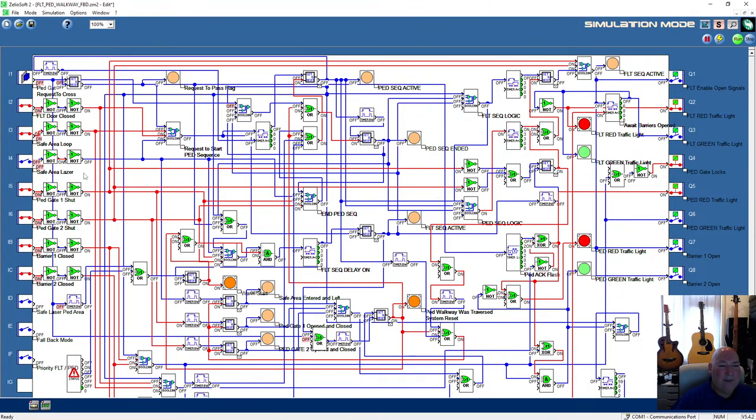So what we need to happen is if it times out, I've got to be so careful, because that's why we need a separate loop. At the minute, this loop does the pedestrian area, and it's one output. It does all the way up to the door where the forklift truck could be. So I don't know from this. If that was the forklift truck, you'd want the gates to be locked, the ped gate to be locked. You definitely want that. You wouldn't want to be releasing the ped gate lock.